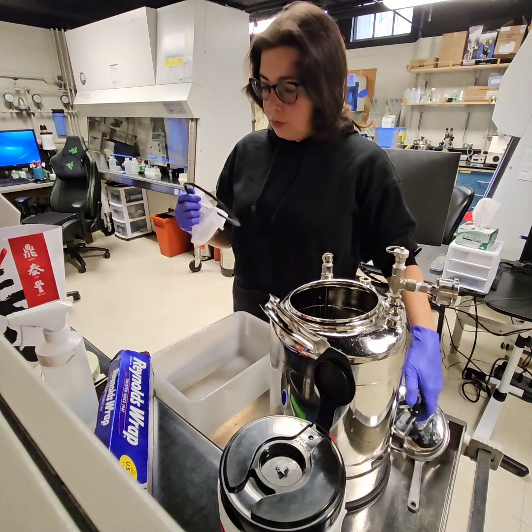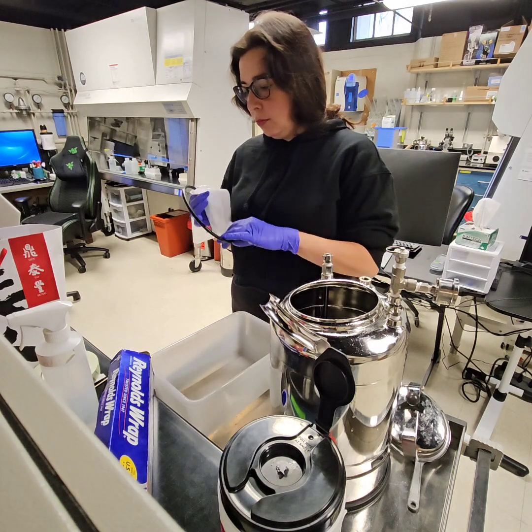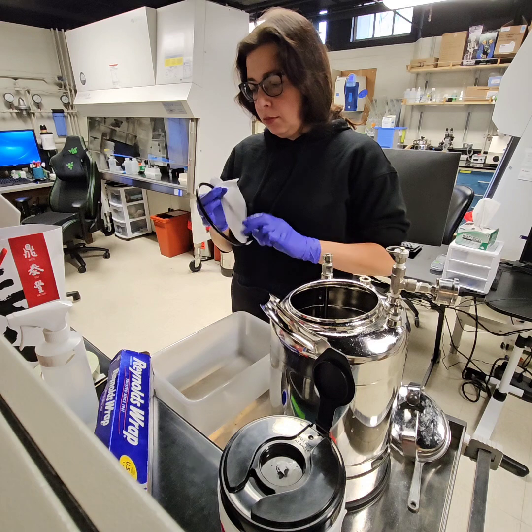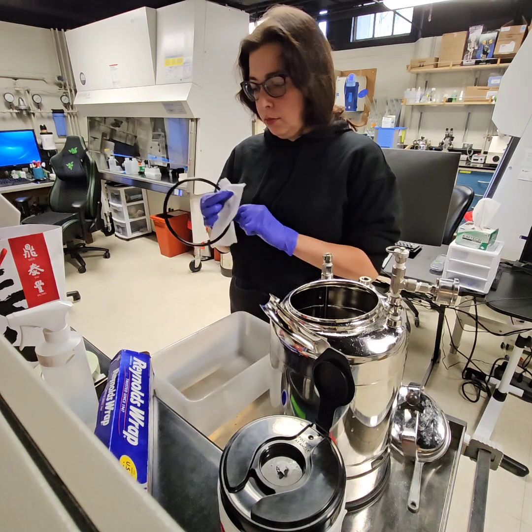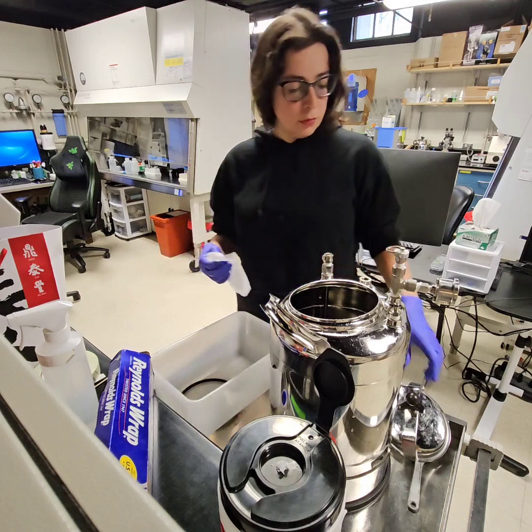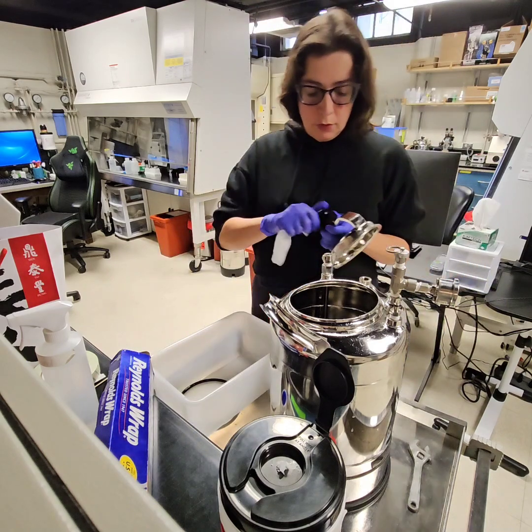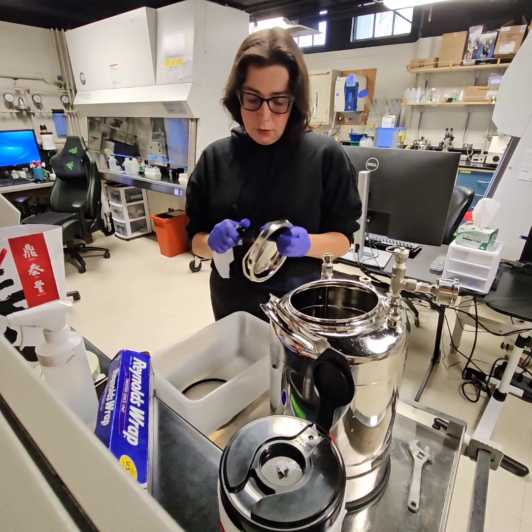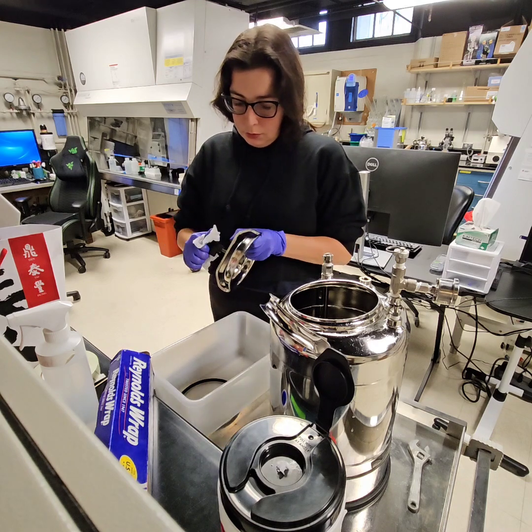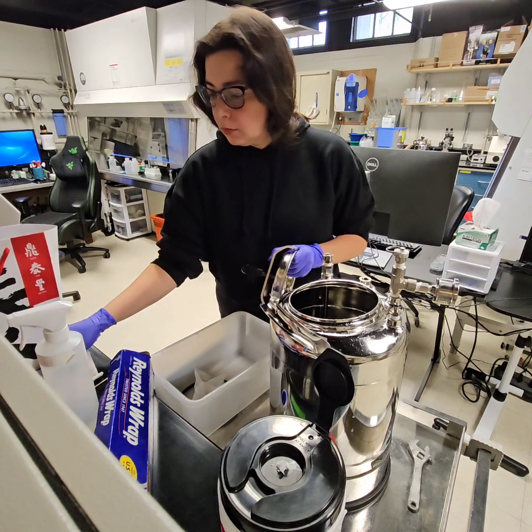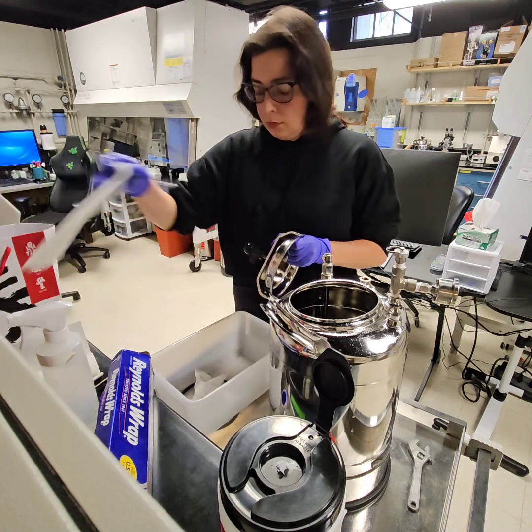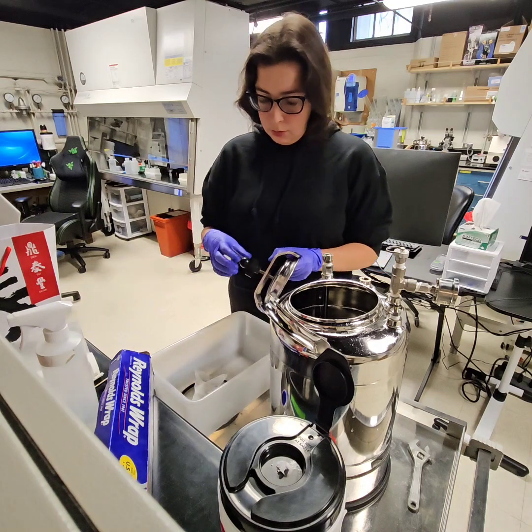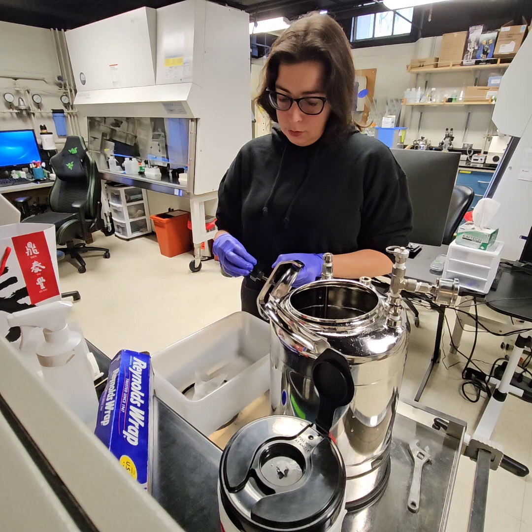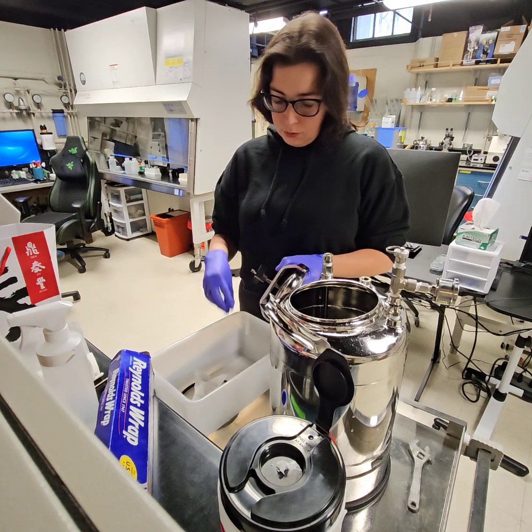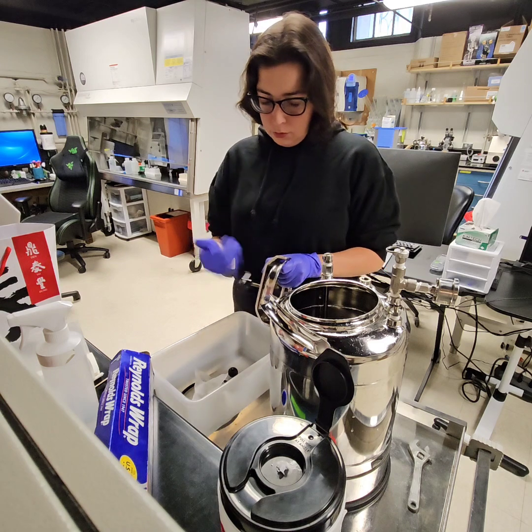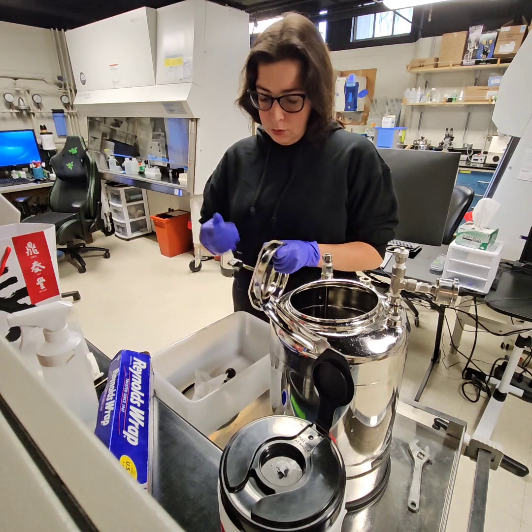So right now I'm removing the O-ring from the lid, and I'm just taking a Kimwipe and removing any dirt, any extra sheath fluid that is dried out on it, and I'm also monitoring it for any cracks that may have formed in the rubber. So not just visually, but also by feeling it with my fingers, if there's any sort of crack within that rubber. So now I'm just kind of wiping it down. I can't really get it off that easily, the top little bulb on the lid, so I just got a paper towel so that I could easily remove it. And so now I'm taking these bulb and other knob off and placing them in the container. You can see it takes a minute.